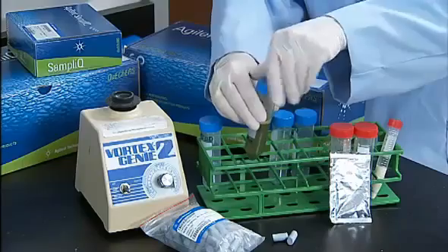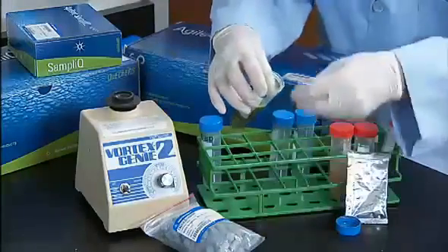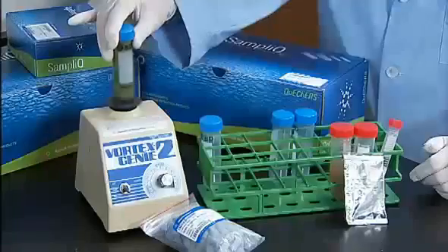Good column hygiene is important to prolong the lifetime of an HPLC column. A column used for analysis of clean samples should last for 1,000 or more injections. An HPLC column used for dirty samples, such as plasma, urine, or other biological fluids, environmental samples, or other samples with messy matrices, may last only a few tens of injections or less without good sample cleanup. Use sample cleanup, such as solid phase extraction, also called SPE, liquid-liquid extraction, or protein precipitation before injection.